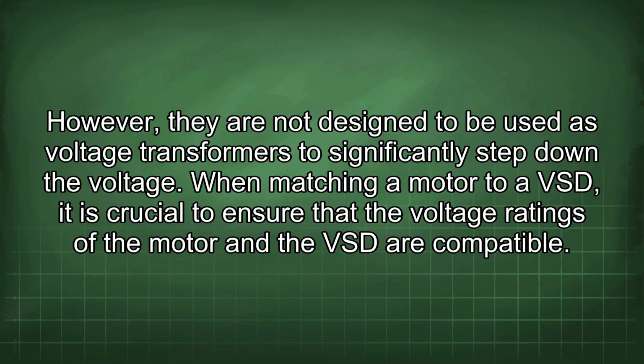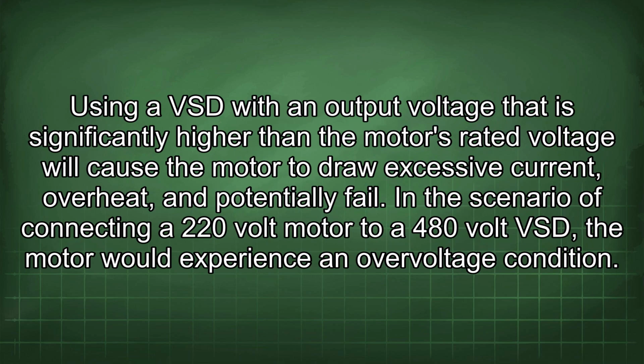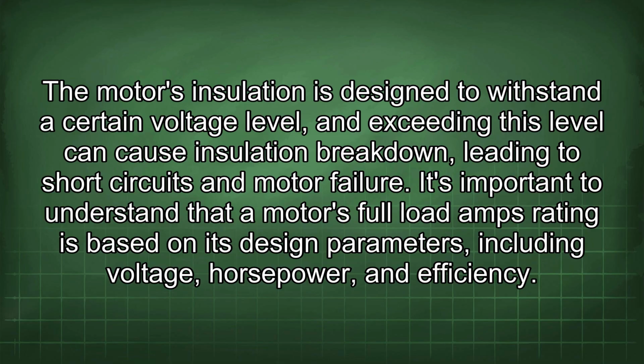When matching a motor to a VSD, it is crucial to ensure that the voltage ratings of the motor and the VSD are compatible. Using a VSD with an output voltage that is significantly higher than the motor's rated voltage will cause the motor to draw excessive current, overheat, and potentially fail. In the scenario of connecting a 220-volt motor to a 480-volt VSD, the motor would experience an overvoltage condition. The motor's insulation is designed to withstand a certain voltage level, and exceeding this level can cause insulation breakdown, leading to short circuits and motor failure.